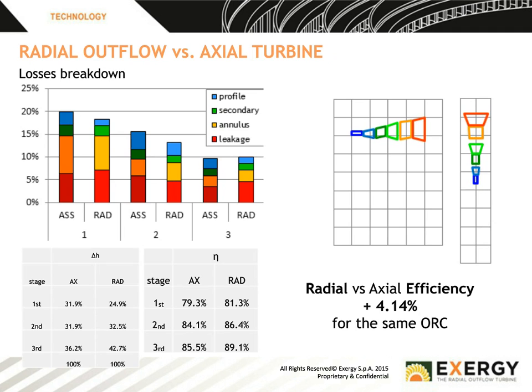So this is a study done to show the difference in efficiencies between radial and axial efficiency. And this was actually a study done by the Politecnico of Milan, and this was done as an academic study. So this is theoretically, when we were being very conservative, we found that each stage of the unit could be a few percent higher efficiency, up to about 4% higher efficiency. But as I said, we can also give more stages. So if we have each stage operating at a higher level of efficiency, but then we give more stages, we can overall have a significantly more efficient turbine. As I said, up to about 7 to 9% more efficient than an axial turbine.